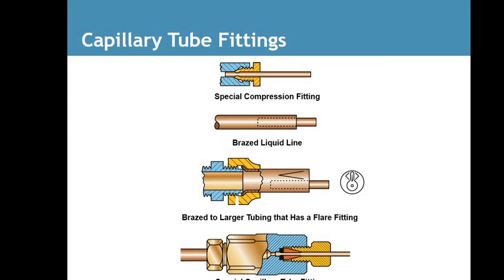Capillary tube fittings. You have compression rings, which is normally what you see in water or plumbing. You have a brazed liquid line, so you can have that liquid line coming to it. You put that capillary tube to the inside of it. You size it down. You can crimp it off and solder it. There's tube that has flare fittings that you can braze onto, and there's a special combination of pieces. The bottom one is what Trane used to use on their systems. These special two-way nuts. It's kind of an odd setup, but they were the ones that used those.